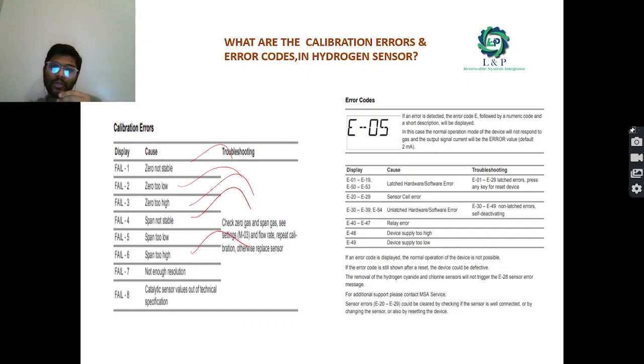And what are the different error codes? If there is any software error or latched hardware error, the errors will be E01 to E19, E50, E53. If it is a sensor cell error, it will be E20 to E29. If it is E30 to E39, or E54, it is an unlatched hardware or software error. If the device supply is too high, it will show E48. If it is very low, it will show E49. Most importantly, errors 1 to 29 are the latched errors. We can reset the devices and do the troubleshooting for these. And E30 to E49 are non-latched errors, which are self-deactivating errors.